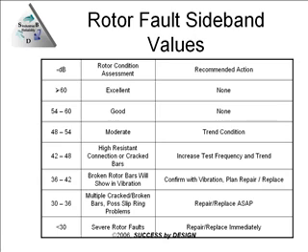Same thing happens with electrical signature analysis. Most permanently mounted CTs do not have the correct reaction that you need for electrical signature analysis, so the results, the peaks will be dampened a little bit. So when you do see the peaks appear, you know that that's an issue that you may want to address.